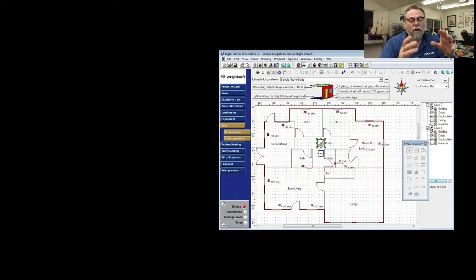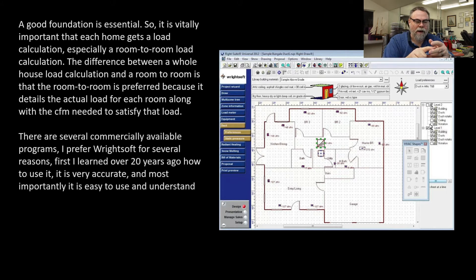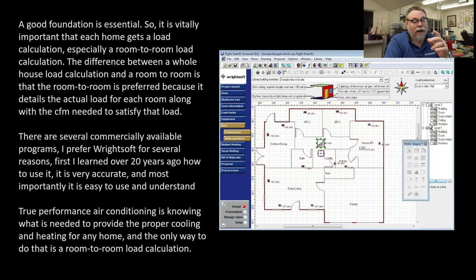Load calculations — there are two types. There's a room-to-room load calculation, and then there's a whole-house load calculation, or a block load. I don't do block loads; I do room-to-rooms. The room-to-rooms tell me how much air is supposed to go into each bedroom and certain parts of the house, and it allows me to size the unit correctly and then size the ductwork correctly. Wrightsoft — which I've been using for 20 years — is very accurate. I can do it very easily and quickly, even on existing homes. If I don't do a load calculation, I don't know how much air is supposed to come out of that register, and I'm just guessing.